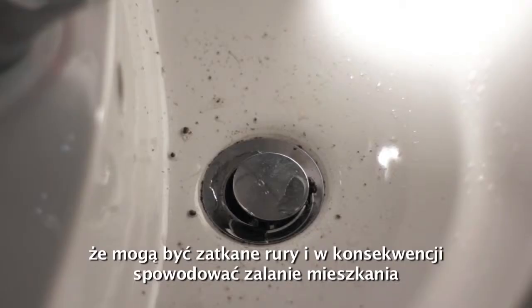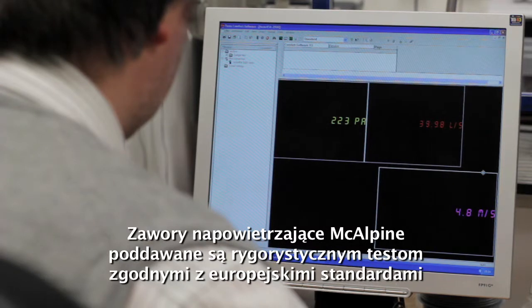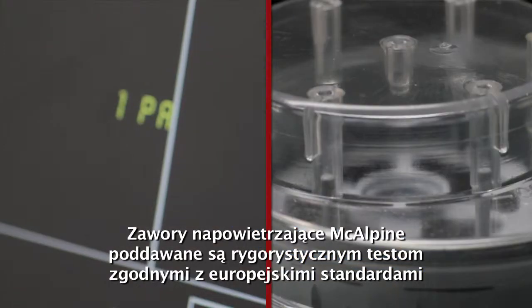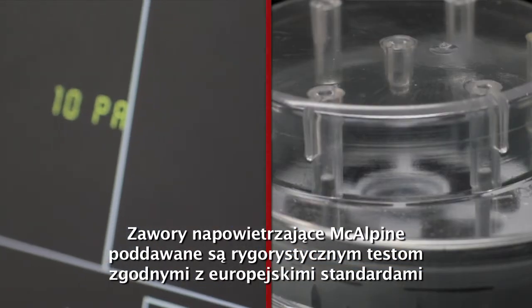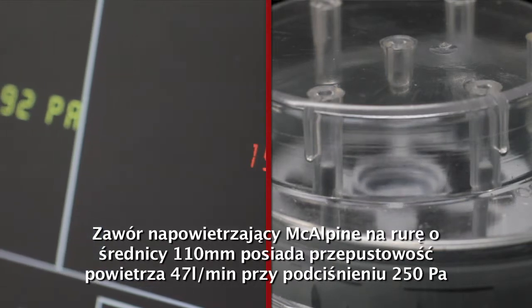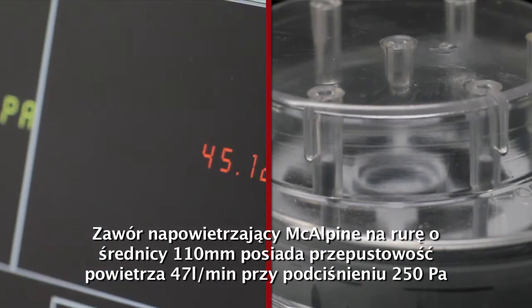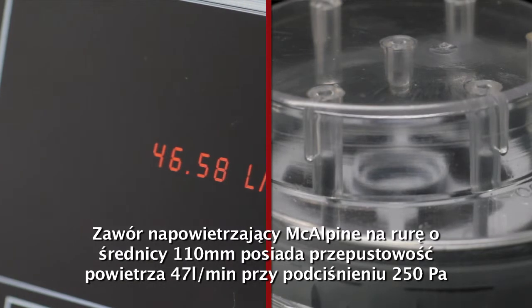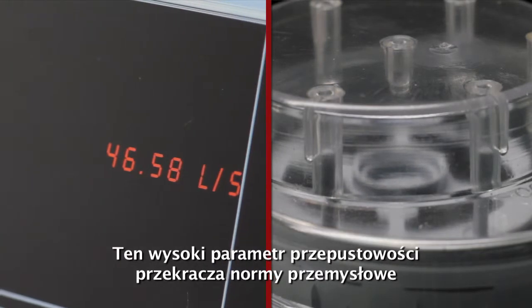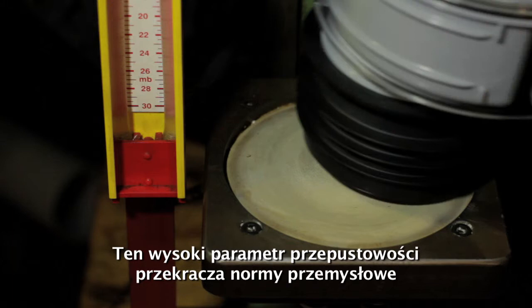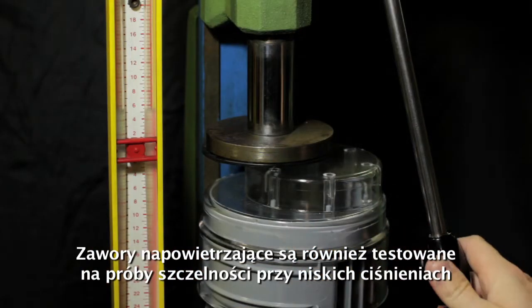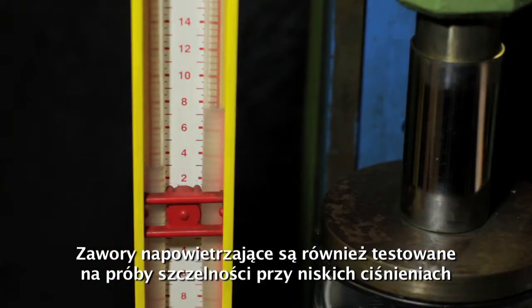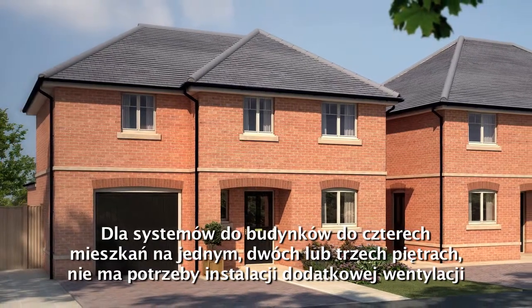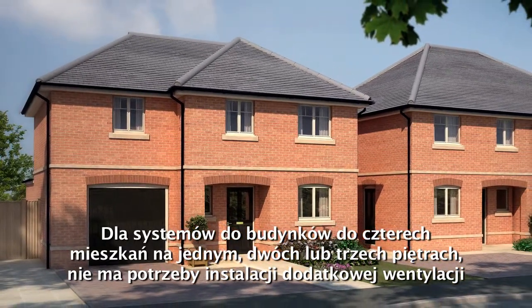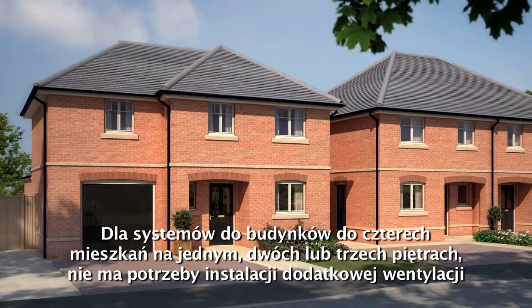McAlpine AAVs are subject to rigorous testing to ensure they comply with European standards. AAVs are also tested to ensure they remain airtight at low pressures. For systems up to and including 4 dwellings that are 1, 2, or 3 stories in height, additional drain venting is not required.